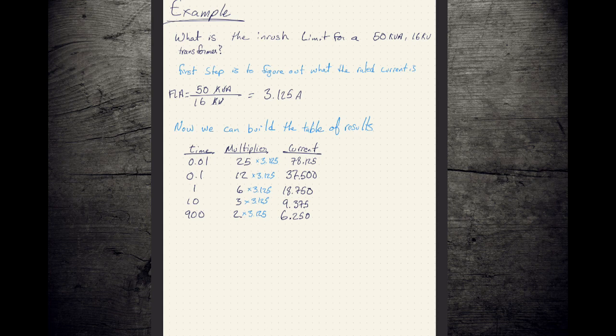So we know what sort of abuse our transformers might be tolerating at the end of a power outage. And we know that obviously our fusing has to be tolerant enough that it would allow this to occur without the fuse operating. But it does lead to the question, well, if a 3 amp transformer can take almost an 80 amp surge, how much more can it take? Like, really, how tough are these things before you damage your transformer?